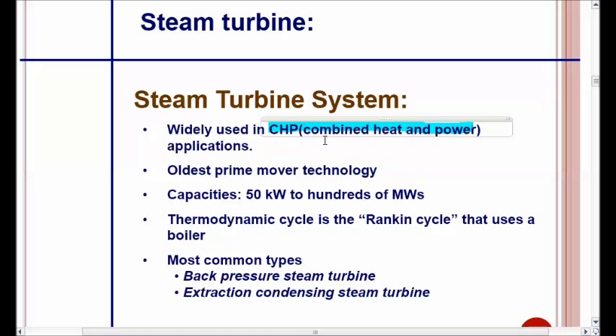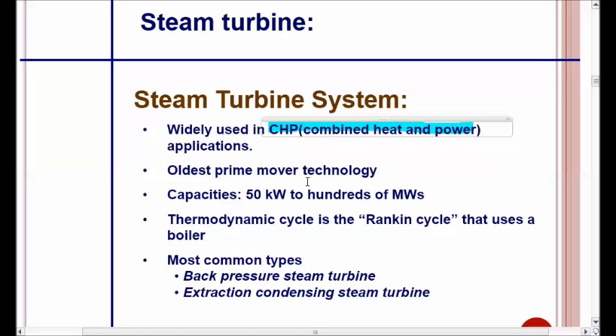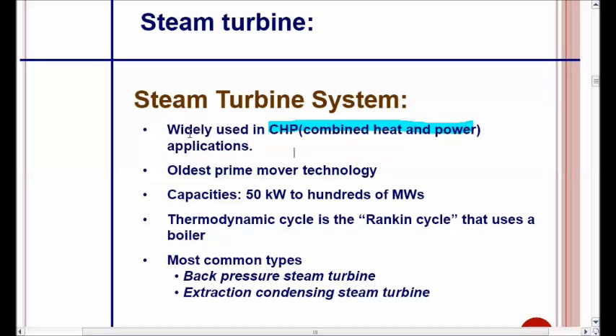Combined heat and power means the application is not only to get electrical output, but also to use the heat exhaust from the turbine for a useful process — for example, a paper and pulp industry or a sugar industry that uses the exhaust steam for their processes, making the efficiency much higher. This is the oldest prime mover technology known to humankind, ranging from 50 kilowatts to hundreds of megawatts. The thermodynamic cycle is based on the Rankine cycle, and the most common types are the back-pressure steam turbine and the extraction condensing steam turbine.